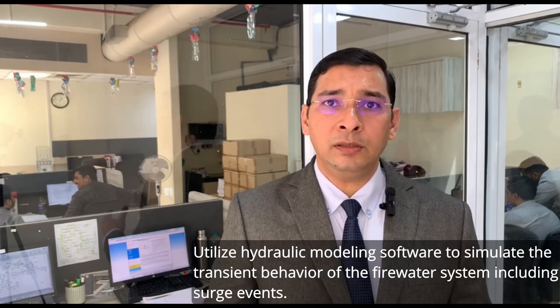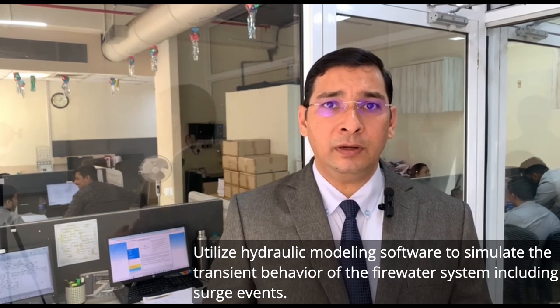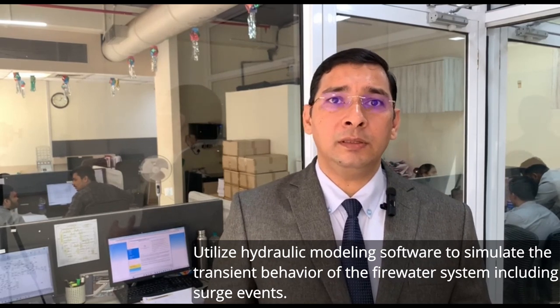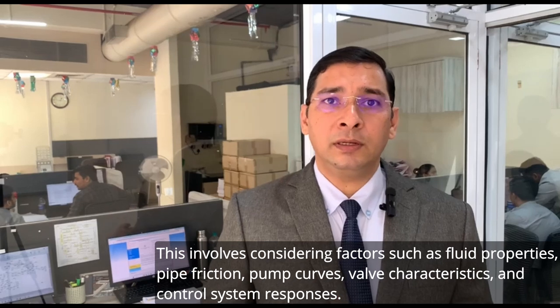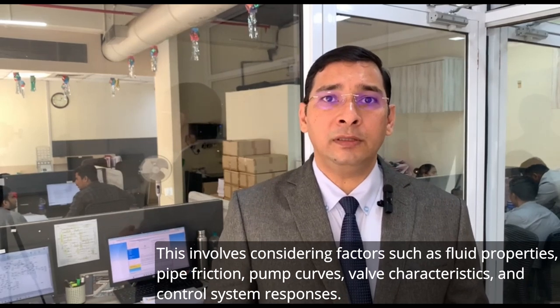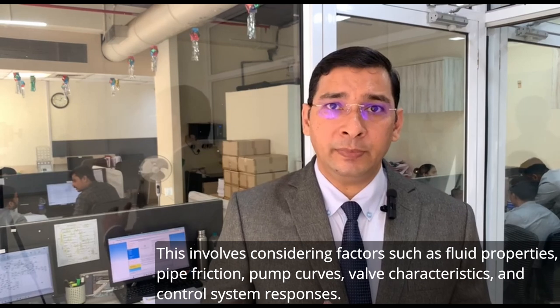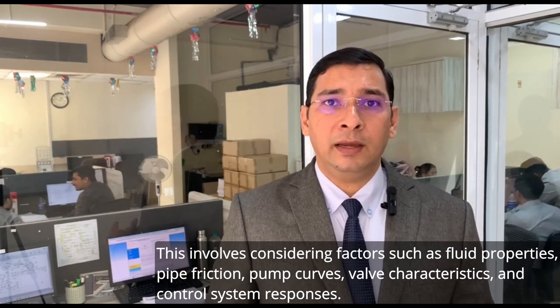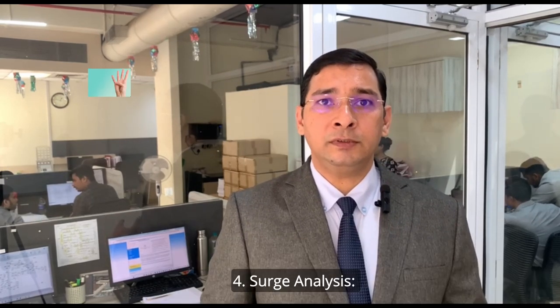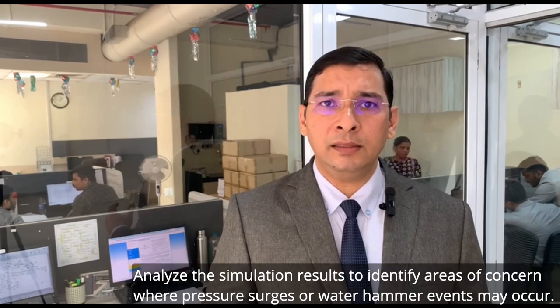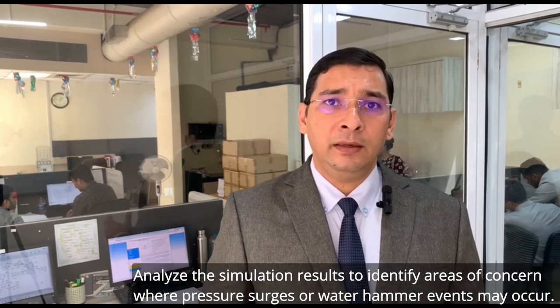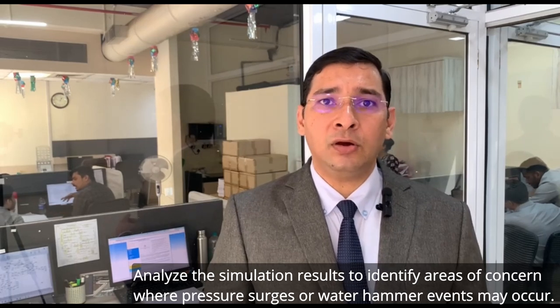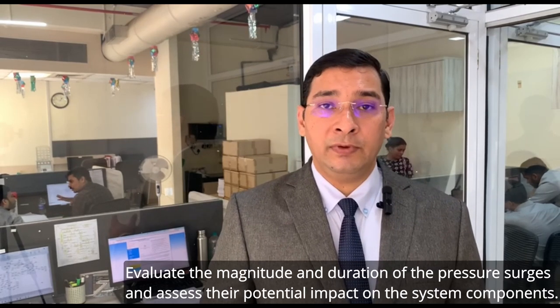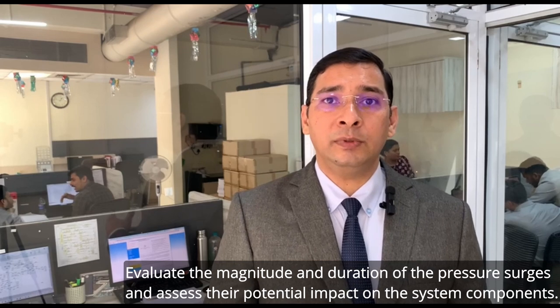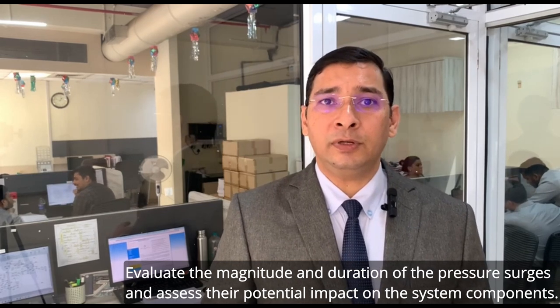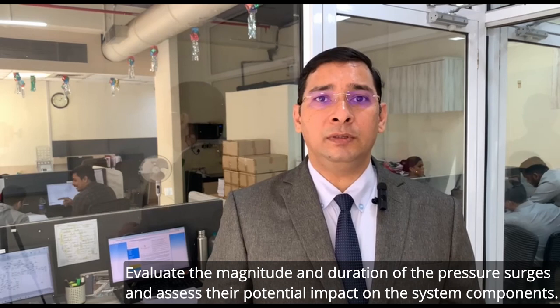Utilize hydraulic modeling software to simulate the transient behavior of the firewater system, including surge events. This involves considering factors such as fluid properties, pipe friction, pump curve, valve characteristics, and control system responses. Fourth step is the surge analysis. Analyze the simulation results to identify areas of concern where pressure surges or water hammer events may occur. Evaluate the magnitude and the duration of the pressure surges and assess their potential impact on the system components.